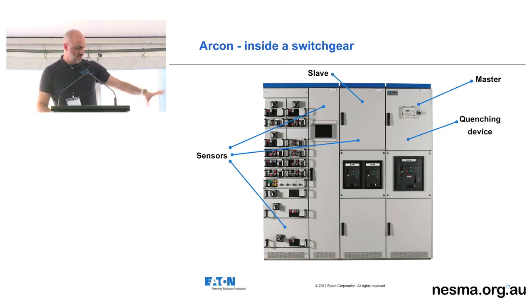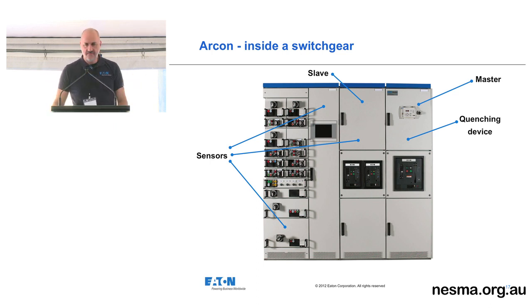So in the system itself, the quenching device you see is allocated in the space above the main incomer. You can put your slaves in various functional units around the board. From there you've got, like I said, your optic fibres out to cover all your main and distribution bars around the system.